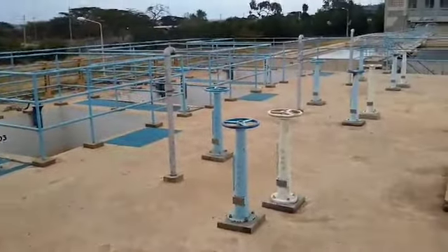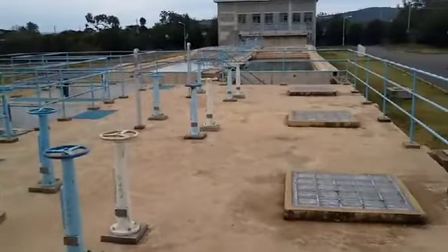Rapid filters. This is a filtration method used in conventional water treatment. Solids that are not separated at sedimentation are removed by rapid sand filters. When the filters are full of trapped solids, they are backwashed, where clean water and air are reverse pumped up the filter to dislodge the trapped solids. Air scouring is used to agitate the particles settled in the sand filters before backwashing.